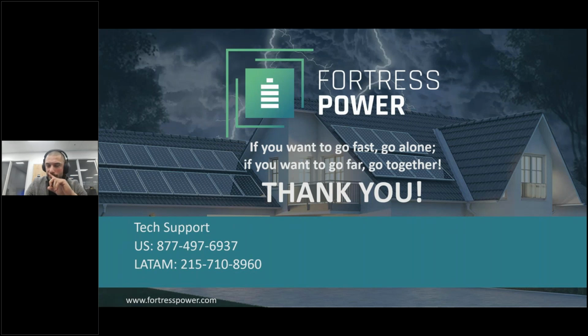Let's say you can parallel eFlex to eFlex - I'm not sure if you're referring to the eFlex Classic. If you're referring to eFlex Classic, we definitely recommend a bus bar, and then from that bus bar you're going to go to the MV. If you're talking about eFlex Max, it comes included with a bus bar already, so you would parallel eFlex Max to eFlex Max with a flexible bus bar, and then from the eFlex Max Master, you would then go to the MV.